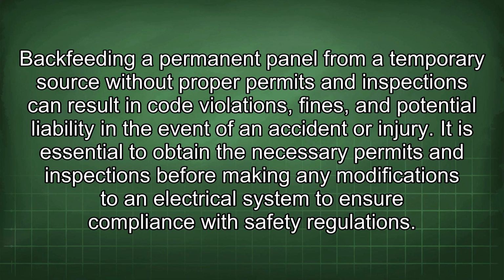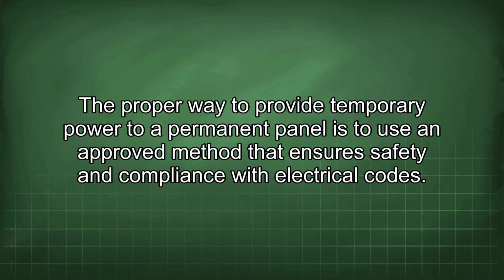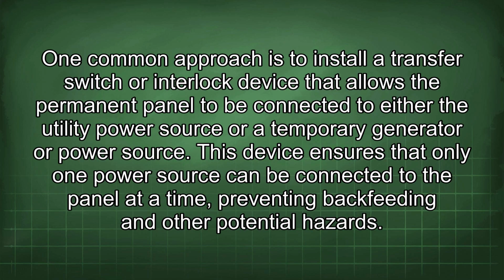compliance with safety regulations. The proper way to provide temporary power to a permanent panel is to use an approved method that ensures safety and compliance with electrical codes. One common approach is to install a transfer switch or interlock device that allows the permanent panel to be connected to either the utility power source or a temporary generator or power source.